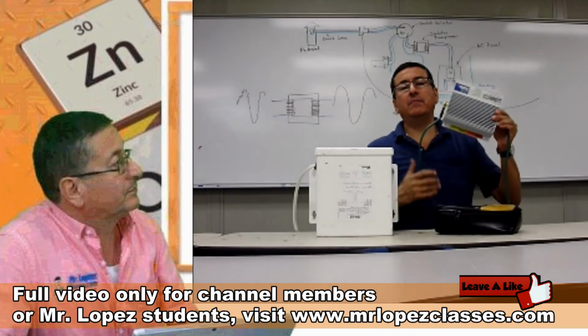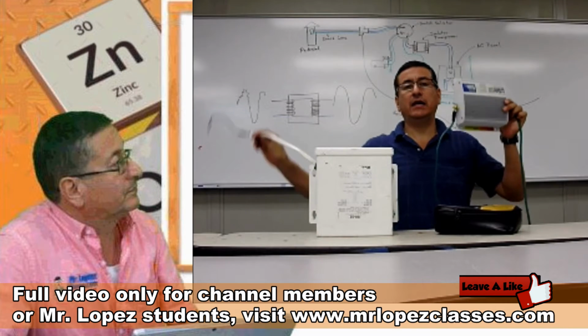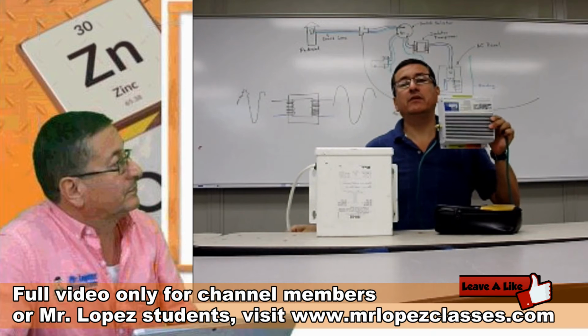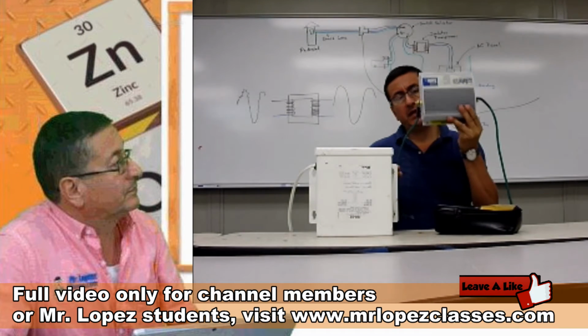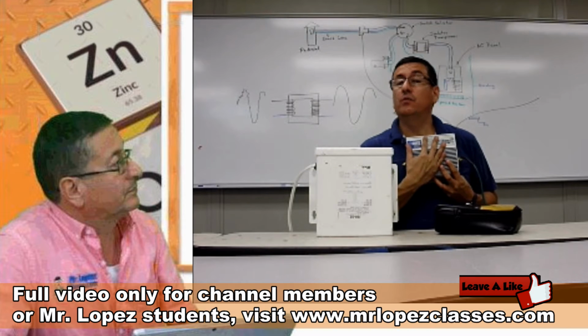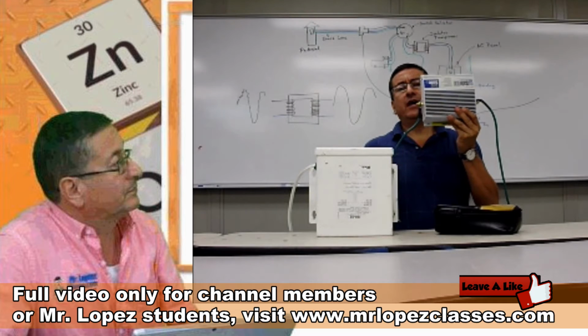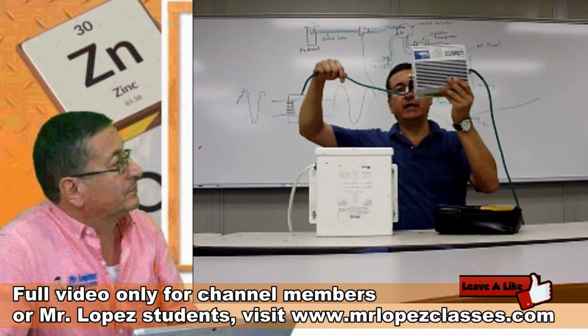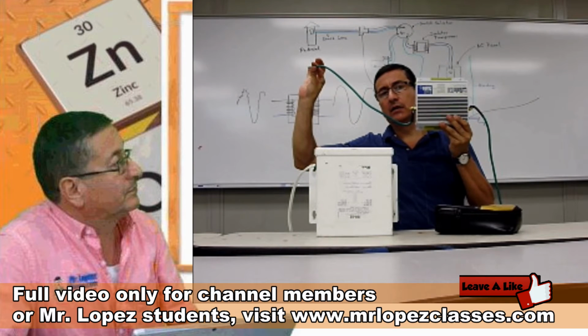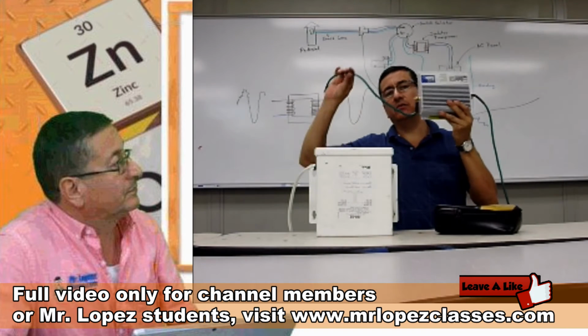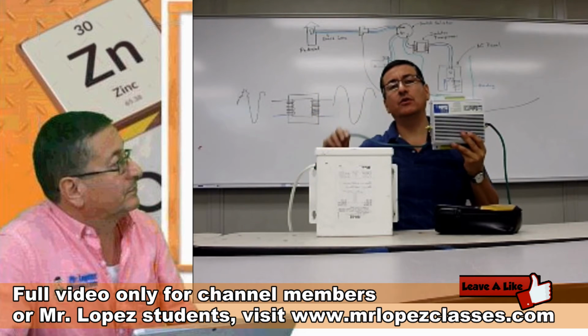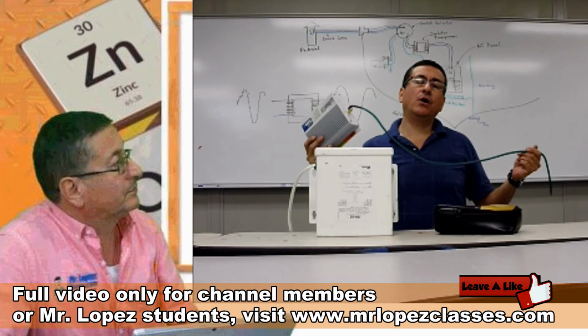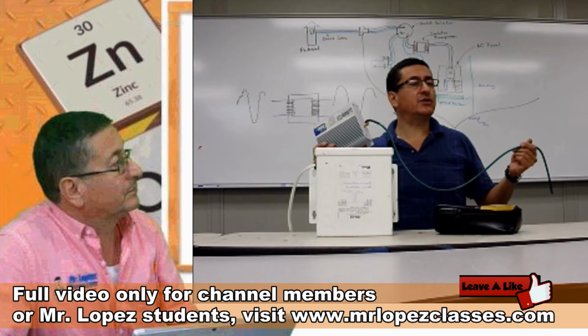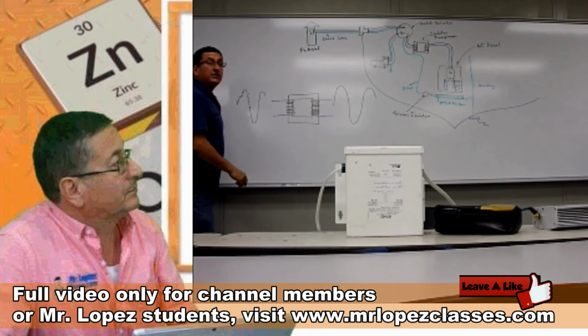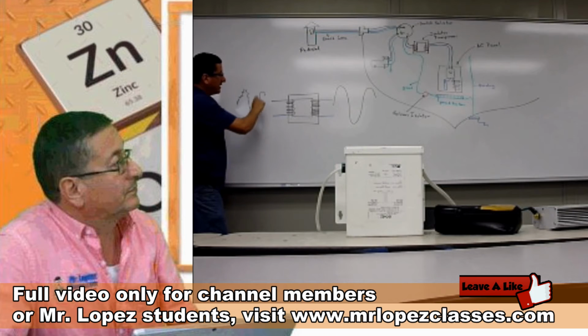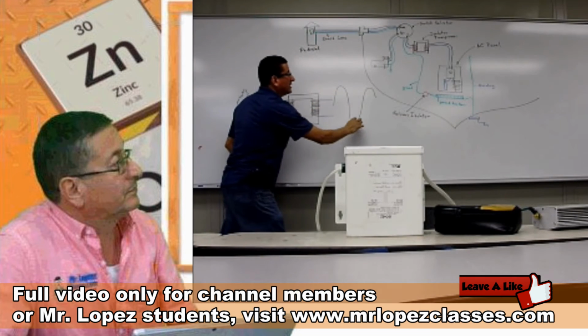I am going to explain the main difference between the galvanic isolator and the isolation transformer. The function is completely different. If you remember, in other videos I explained the procedure to verify if the galvanic isolator is working properly. Basically, the galvanic isolator is inserted in the ground line, the ground that is coming from the shore power entering the boat. If the ground coming from the shore power is contaminated with noise or interference, it enters the boat and creates corrosion and oxidation and damages all the metallic elements inside of the boat. This is the picture for the isolation transformer. The signal is contaminated in the input, and in the output the signal is completely clean.